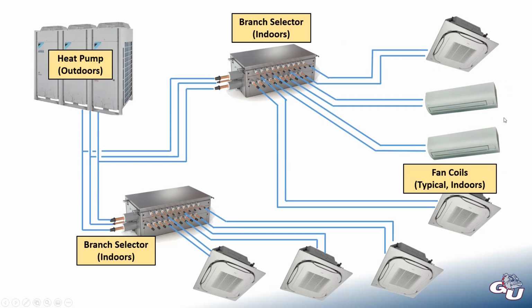This unit right here is designed to be mounted just up on the wall, so you would see this within the space. This pulls air in through the top, runs it through a DX coil, and then blows it out the bottom, either hot air or cold air. And all of this stuff is connected with refrigerant piping. And you might notice that on this side of it, I'm showing 3 pipes, and then everything down here is 2 pipe down to the fan coils. And that has to do with how this system does what's called heat recovery. I'll get more into that here in a moment. But this is the basic schematic.